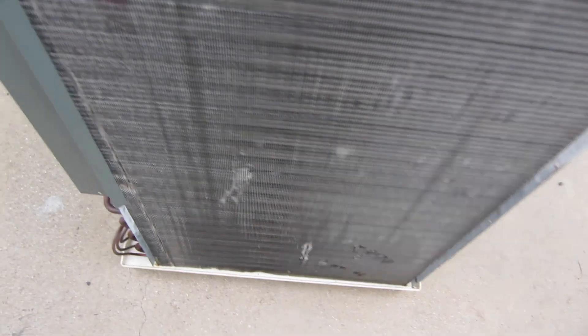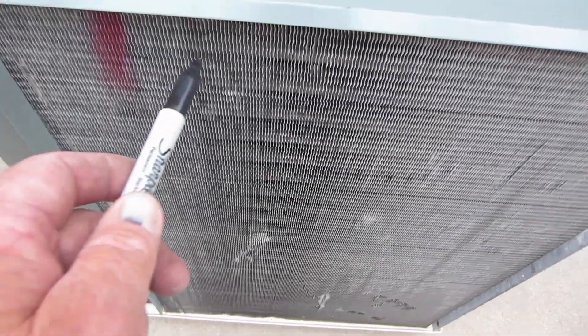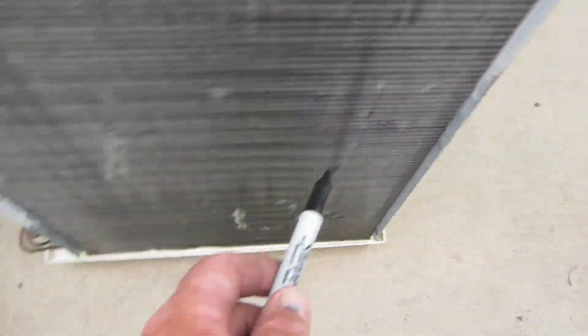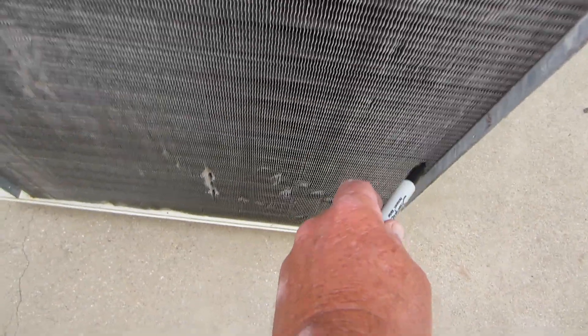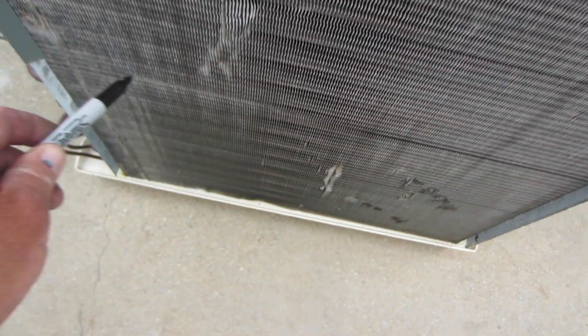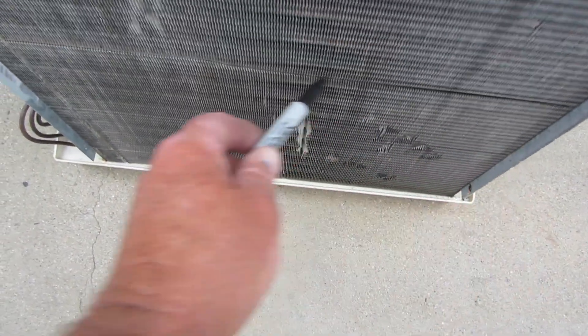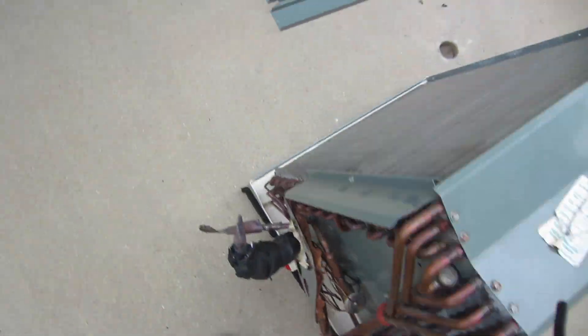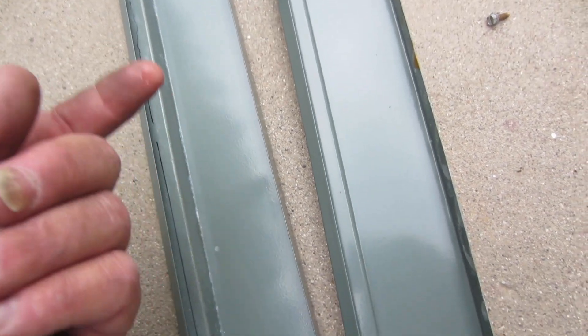Look on the coil here — this row is concerning. It doesn't mark very well, but from here down it's all oil. Our end shields: this one's clean, but this one is all oil right here. I don't know if you can see it, but this is all oil — it's an oil slick.